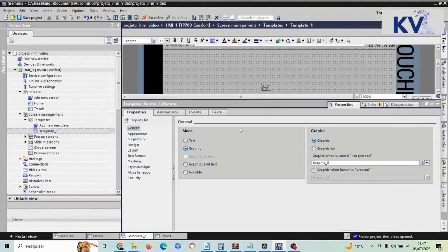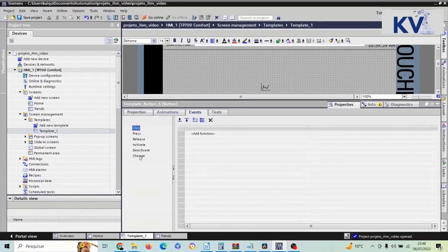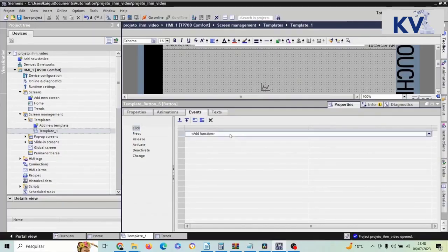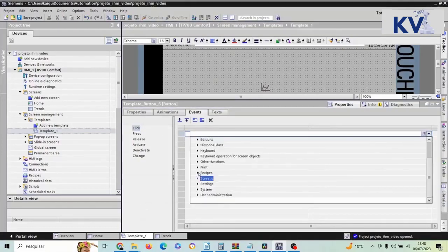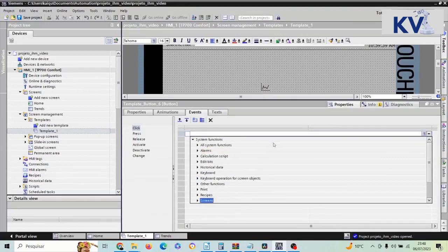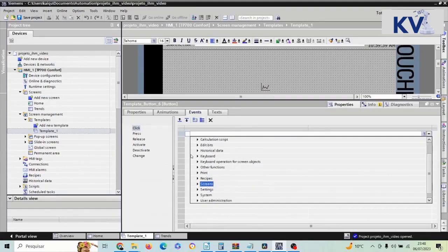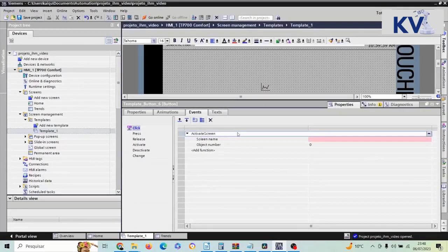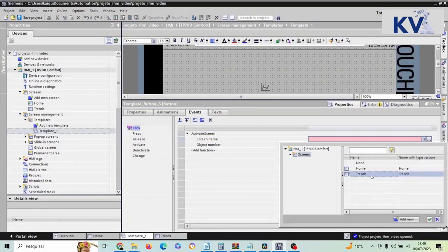Now I'm going to set up the event that will be fired. In Events, there are actions the user can perform to trigger an event — it could be click, pressing the button, releasing the button, or changing the button. In this case, we're going to use Click. When I click, I want an action to be performed: a screen swap. I select it, and from the available actions I go to Screen and choose 'Activate Screen'. The screen I want triggered when I press that button is the Trends screen, so I select it.